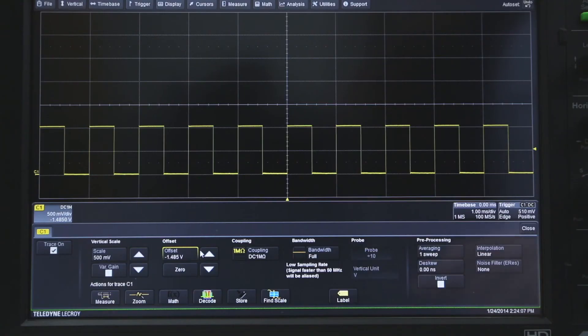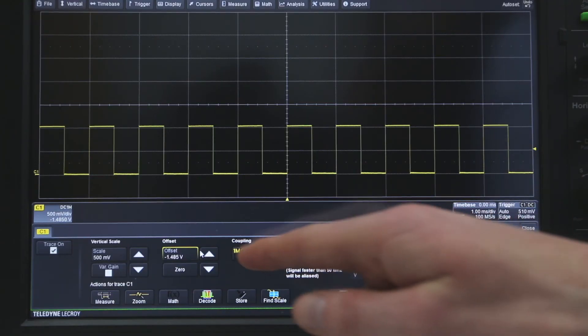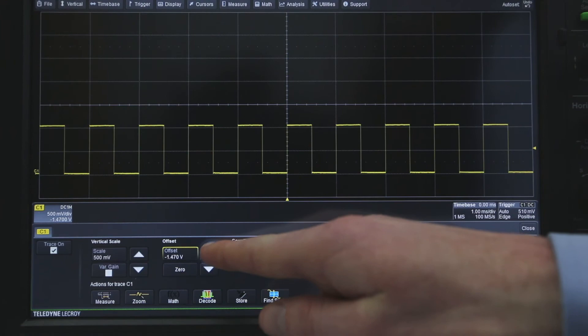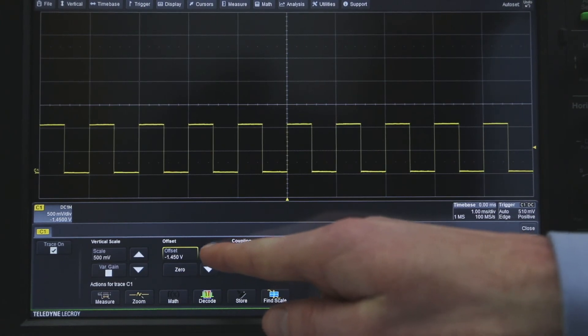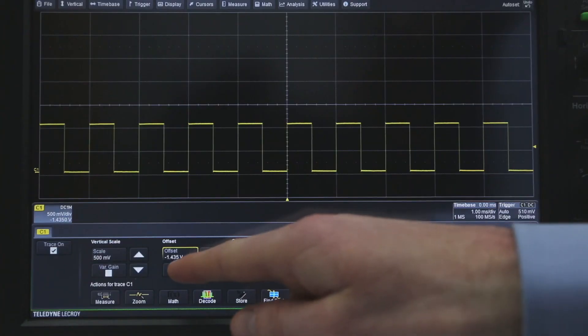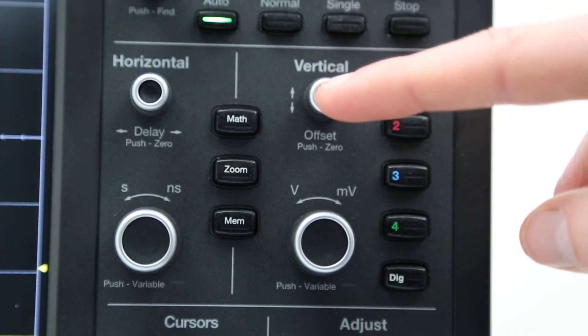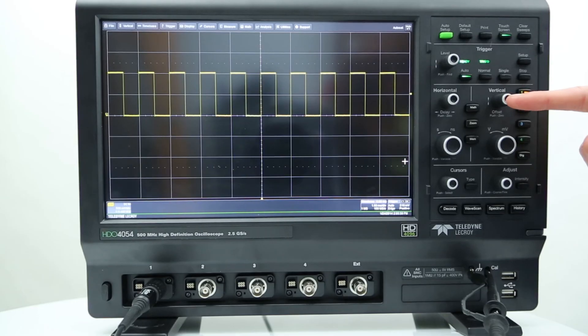Vertical offset can be set by turning the offset front panel control knob or by using the offset controls in the channel dialog box. Pressing the zero button returns the trace to the center of the grid. Pressing the offset front panel control knob has the same effect.